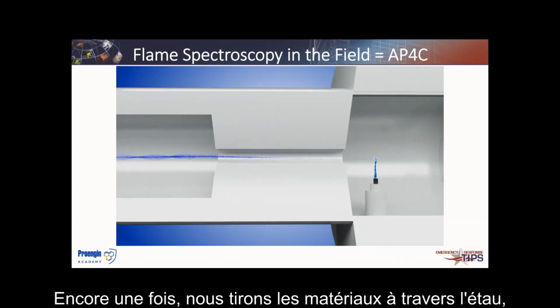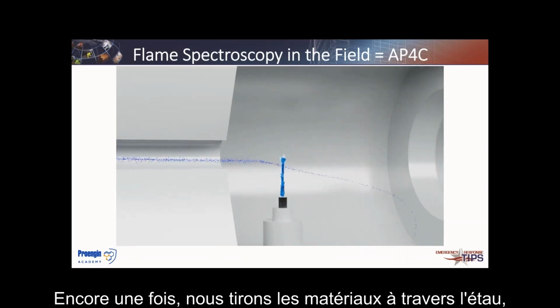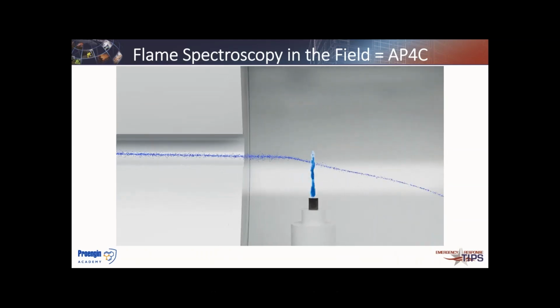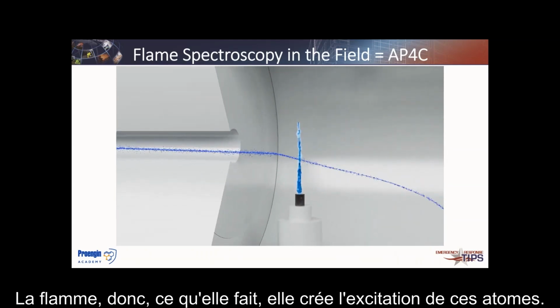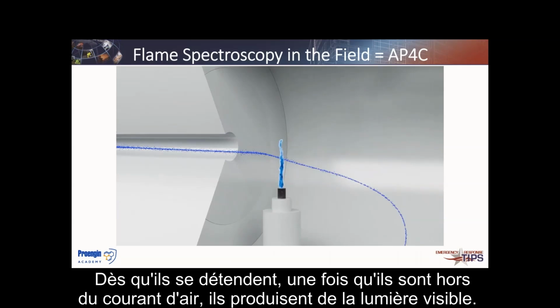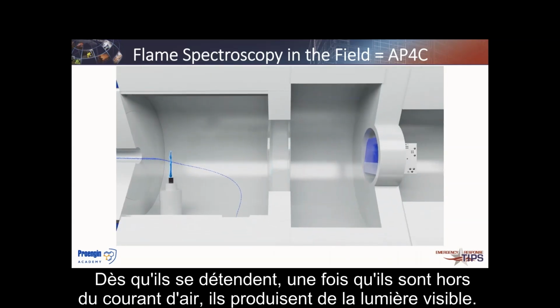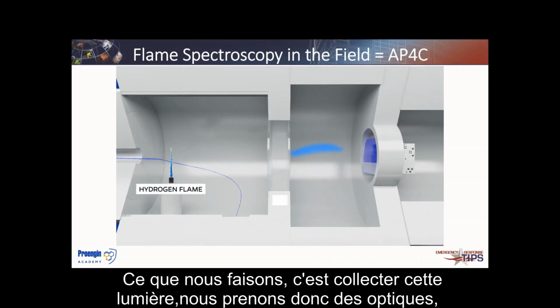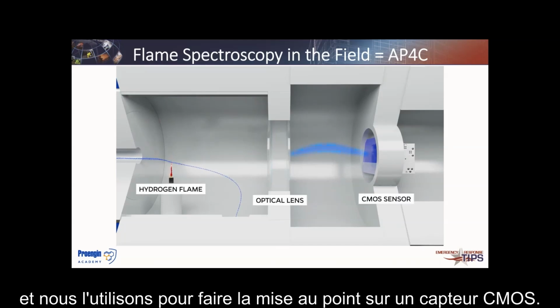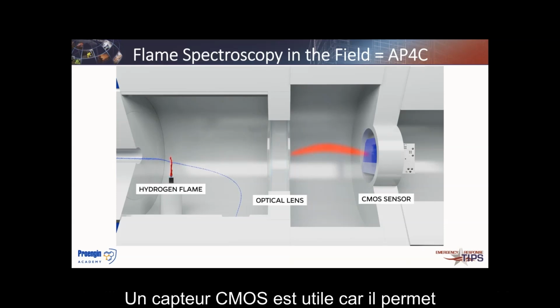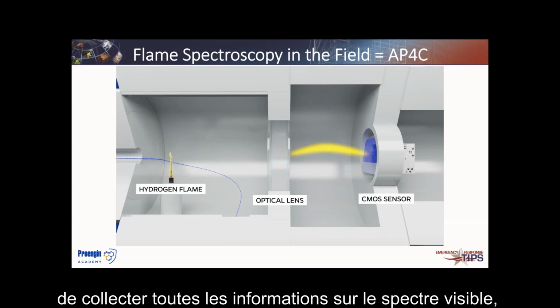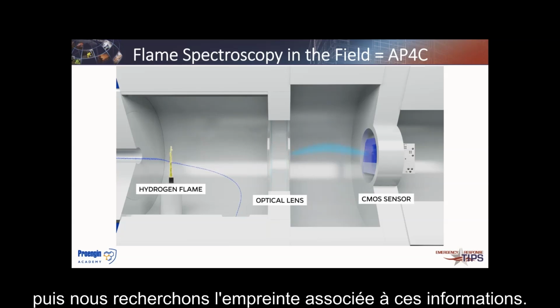So again, we're pulling the materials through the device and exposing them to the flame. The flame creates the excitation of those atoms. As soon as they relax, once they're out of the airstream, they produce visible light. So we collect that light. We take some optics and use them to focus it on a CMOS sensor. A CMOS sensor is helpful because it allows us to collect all the information on the visible spectrum, and then we're looking for the fingerprint associated with that.